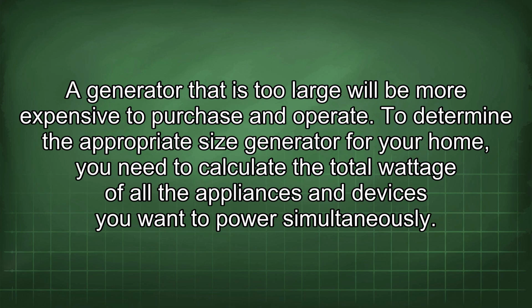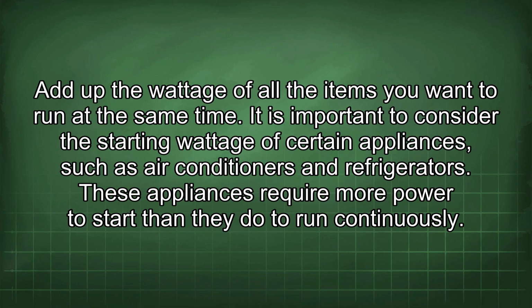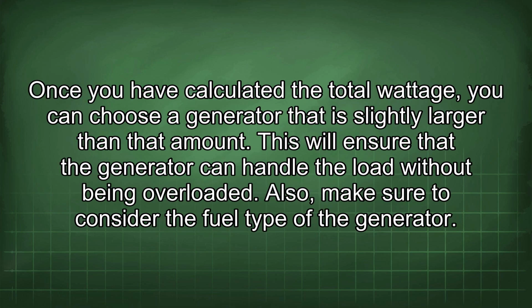To determine the appropriate size generator for your home, you need to calculate the total wattage of all the appliances and devices you want to power simultaneously. Add up the wattage of all the items you want to run at the same time. It is important to consider the starting wattage of certain appliances, such as air conditioners and refrigerators. These appliances require more power to start than they do to run continuously. Once you have calculated the total wattage, you can choose a generator that is slightly larger than that amount. This will ensure that the generator can handle the load without being overloaded.